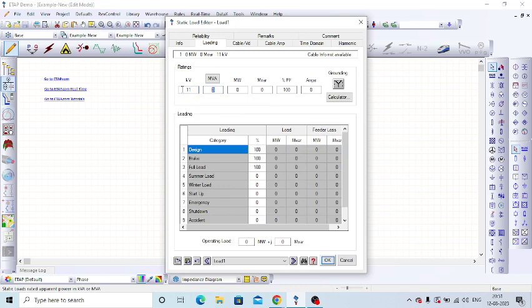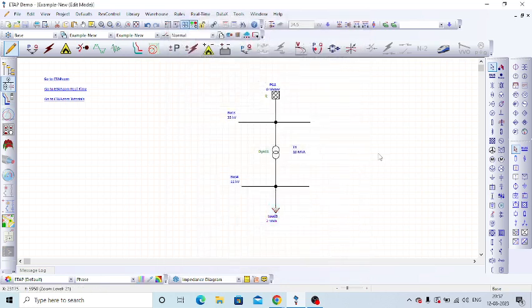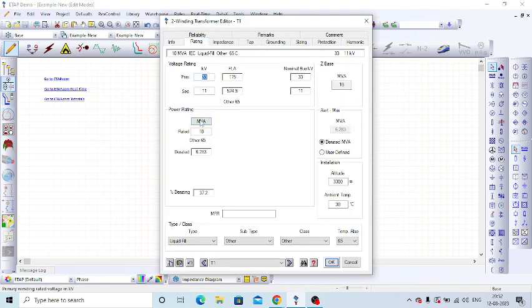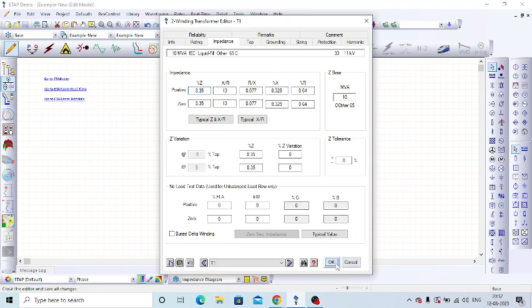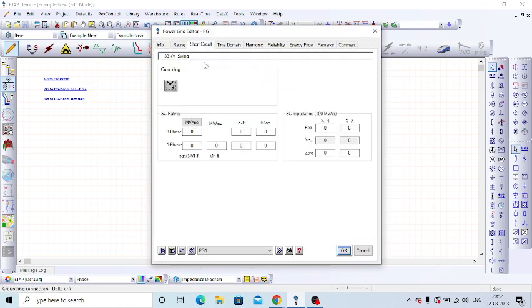So what are the data required for the load flow analysis? Those details we need to enter first. I entered the ID, bus voltage, then in the rating page the transformer MVA, then transformer impedance. Then in addition to that, in the grid we need to update the grid short circuit capacity. It means whenever there is a fault, what is the maximum fault current the grid can contribute. That normally will be in MVA, or sometimes in kilo ampere. Just now I'm considering 1000 MVA as the grid fault current, and the X/R ratio is 14. So it's some atypical value.